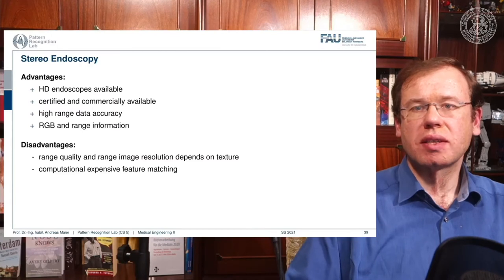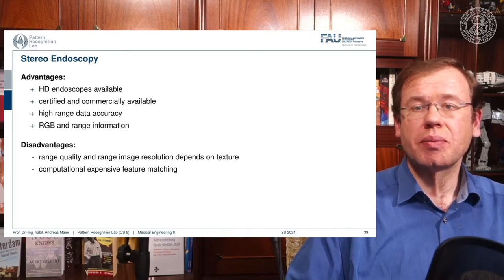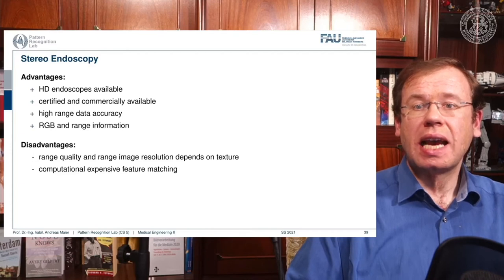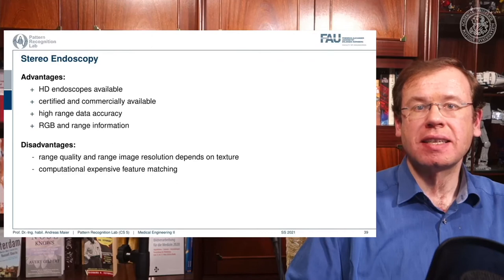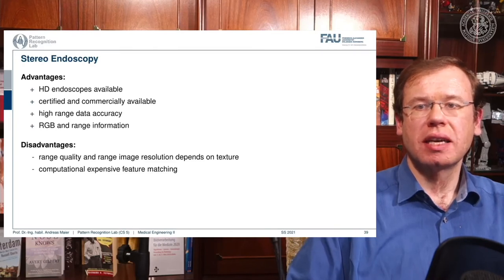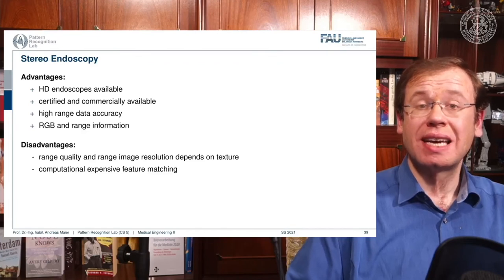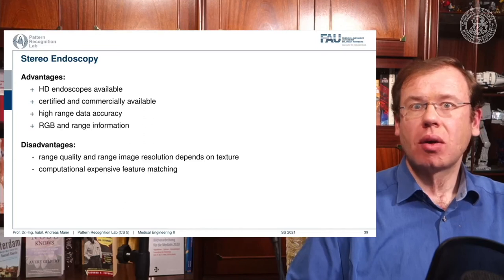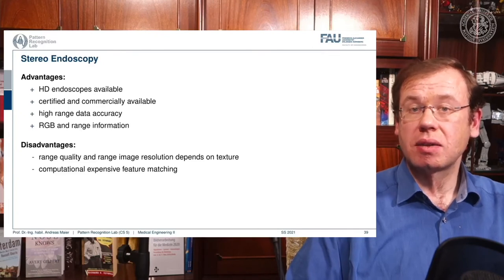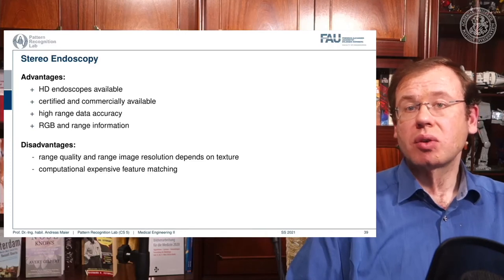This is the key problem of stereo vision. In summary, the advantages are that high-definition endoscopes are already available, certified, and commercially available, with high range data accuracy for depth computation, and you get color (RGB) and depth range information simultaneously. However, the range quality and resolution depend on texture — if you image something without texture, like a white wall or a uniform organ, you will get no depth information. Feature matching is also computationally expensive.